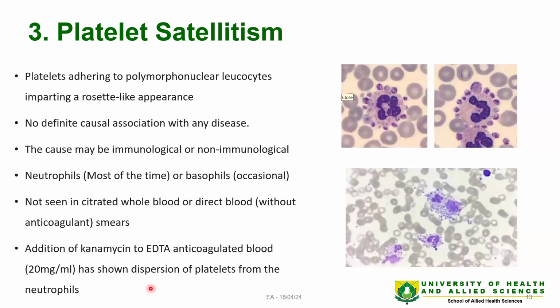It causes dispersion of the platelets from the neutrophil. And so when that has been done, you can rerun your platelet count again on the analyzer, and you would expect the results to be different.